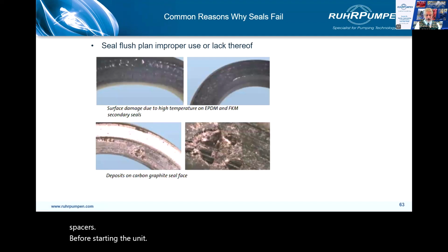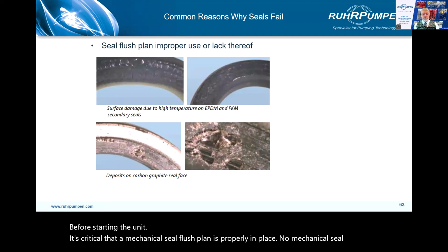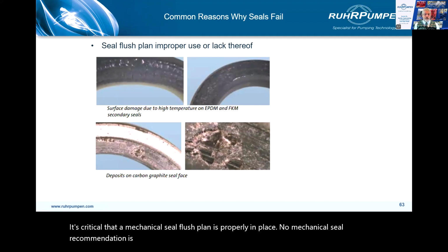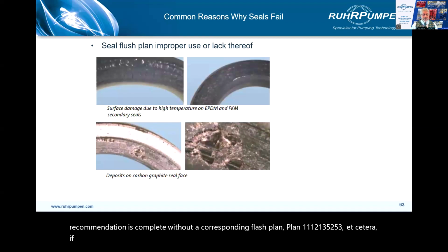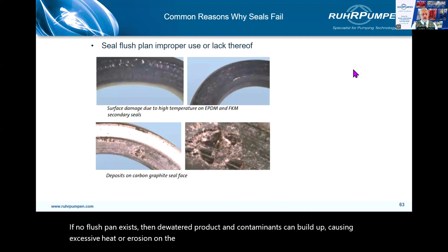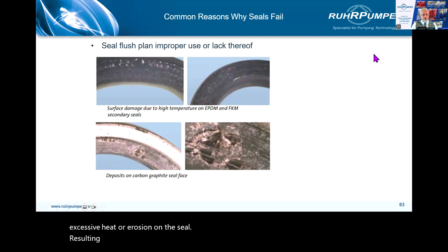It's critical that a mechanical seal flush plan is properly in place. No mechanical seal recommendation is complete without a corresponding flush plan. Plan 11, 12, 13, 52, 53, etc. If no flush plan exists, then dewatered product and contaminants can build up, causing excessive heat or erosion on the seal, resulting in shortened seal life.